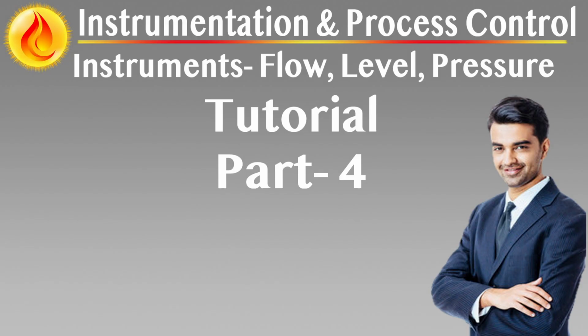Sensor design and response characteristics. Two sensing principles are available. Constant power anemometer, CPA, heats the sensor at fixed power, measures temperature difference. Slow response time, 20 to 60 seconds, suitable for stable background flows, e.g. room air purges. Constant temperature anemometer, CTA, actively adjusts heater current to maintain a set delta T. Fast response time, 1 to 3 seconds, better for control or dynamic gas measurement. The sensor must be fully immersed in the flow stream away from wall effects or stagnant zones. In large ducts or stacks, insertion-style probes may require multi-point arrays to capture representative flow, especially where profiles are irregular.